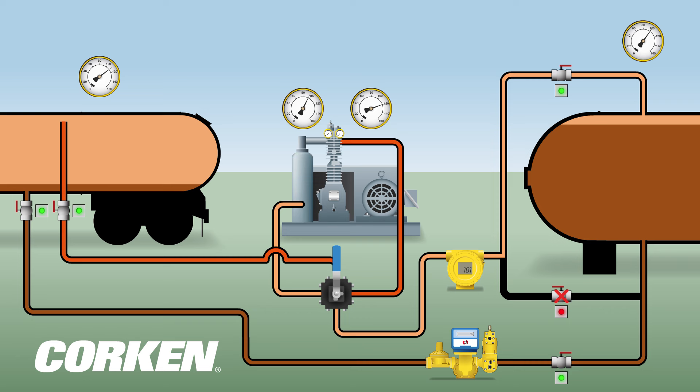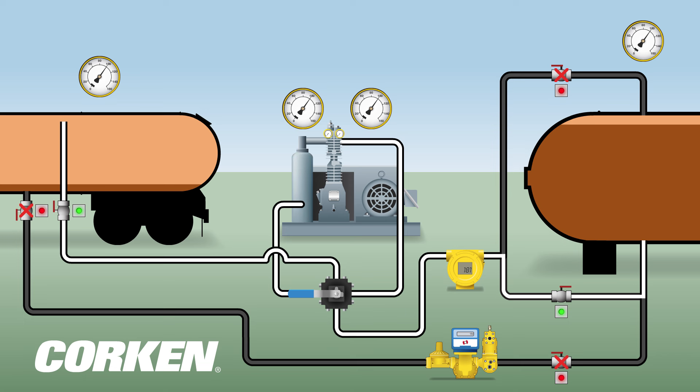The liquid transfer process is now complete. The compressor is turned off to begin the vapor recovery process. The four-way valve is reversed and other valves are opened or closed to facilitate the vapor recovery. The compressor is started and begins to draw the vapor from the transport tank.